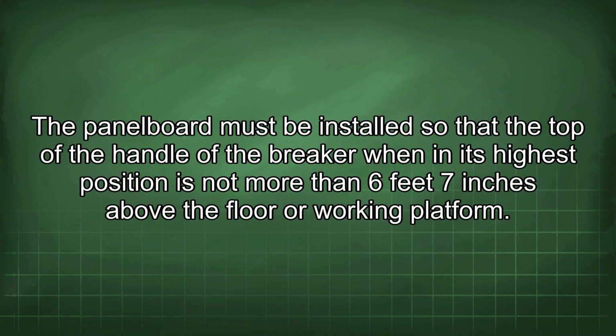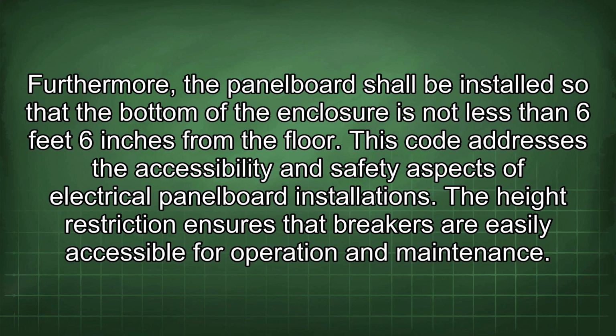The panel board must be installed so that the top of the handle of the breaker, when in its highest position, is not more than 6 feet 7 inches above the floor or working platform. Furthermore, the panel board shall be installed so that the bottom of the enclosure is not less than 6 feet 6 inches from the floor.